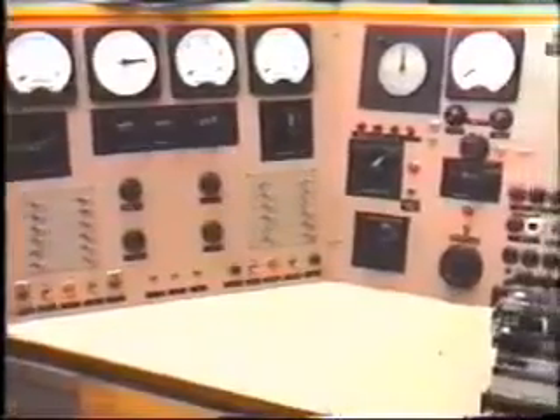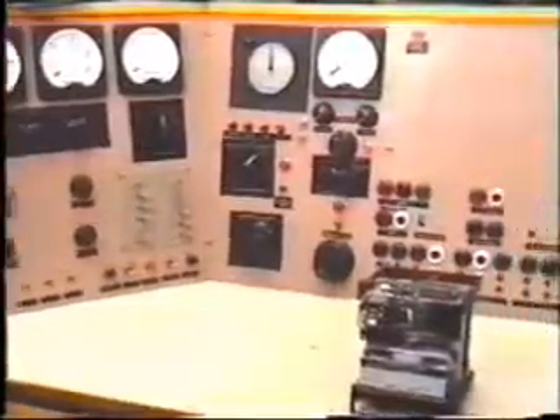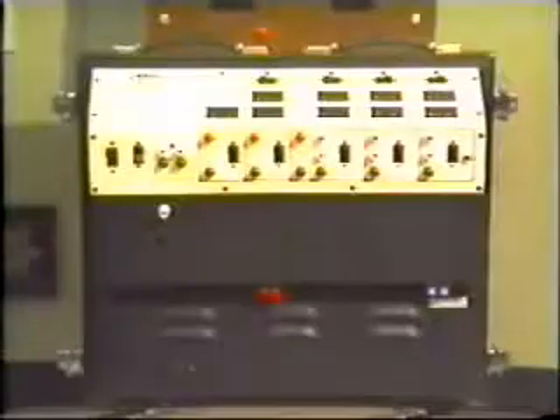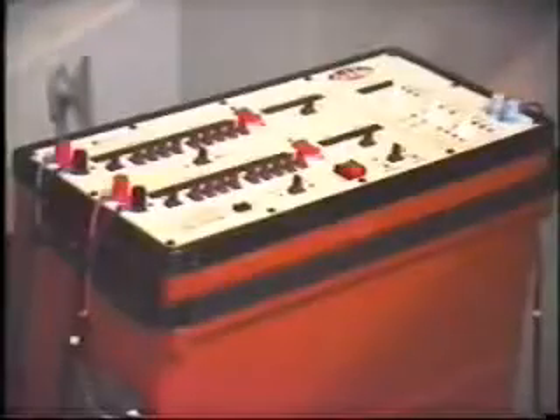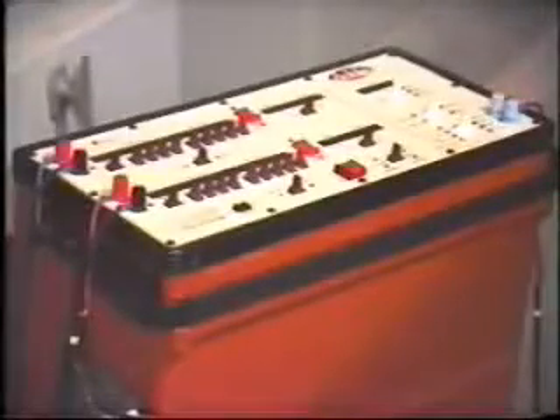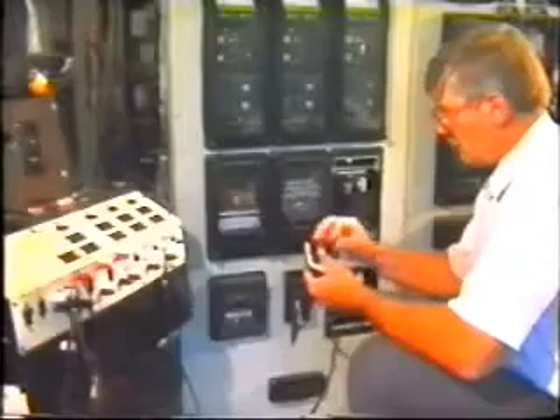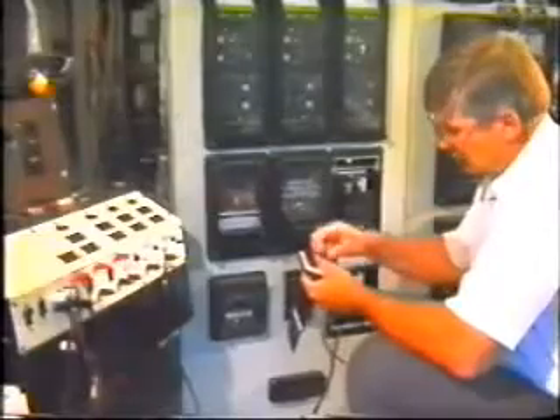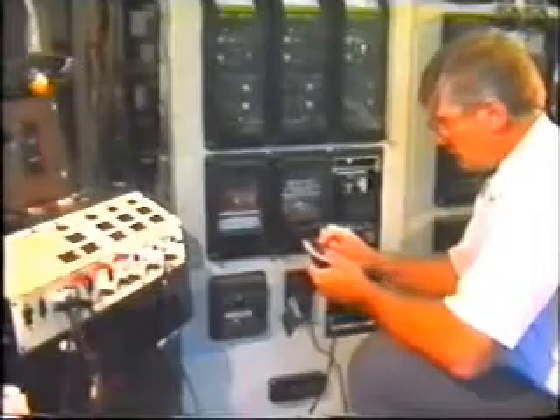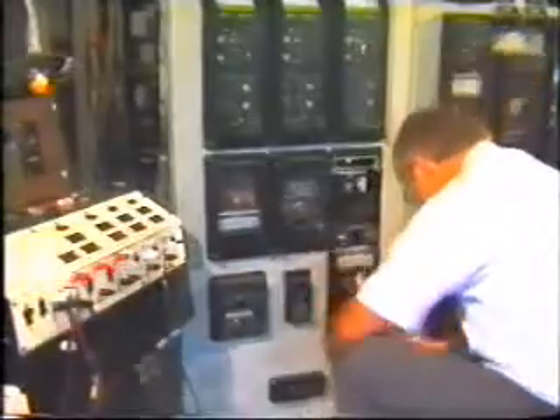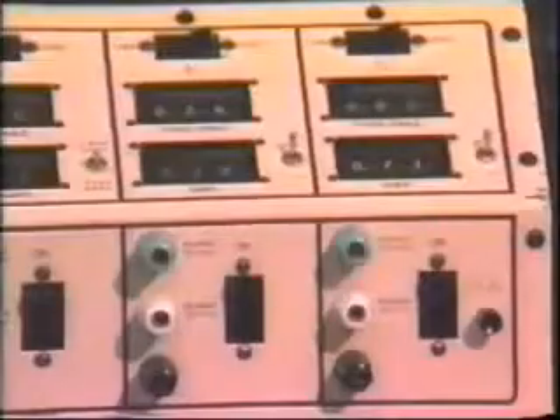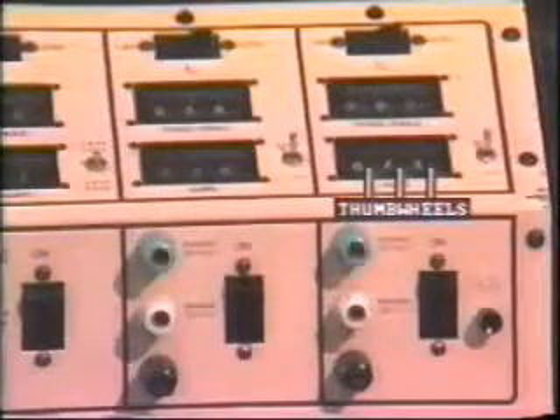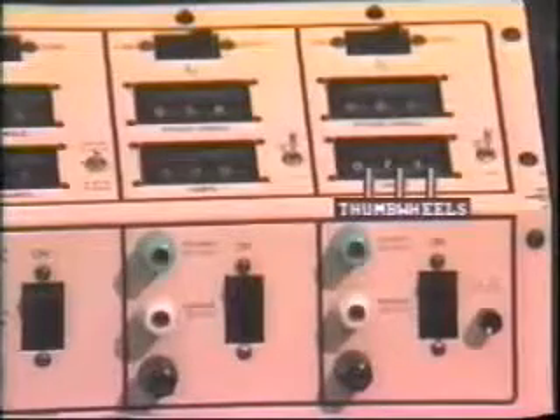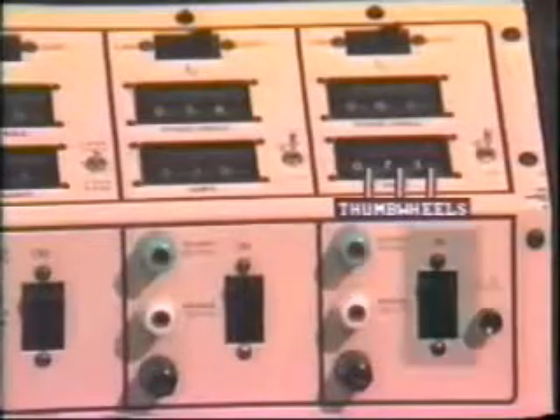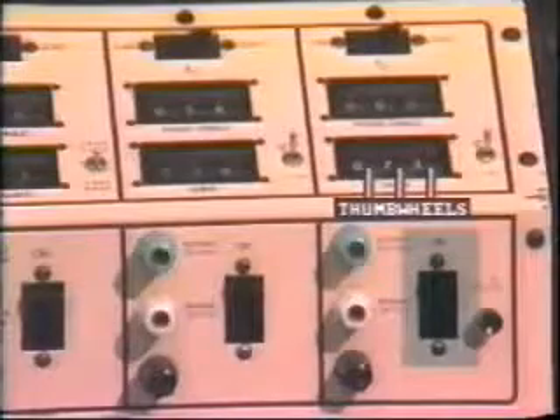Over the past 20 years, this traditional type of test set has been superseded first by solid state and now by digital equipment. A solid state test set allows us to plug into a 120 volt AC single phase source and produce three-phase voltage and current quantities at any phase angle and amplitude desired. Adjustment is by means of thumb wheel adjustments within the test set's limits. Each output source has its own on-off switch.